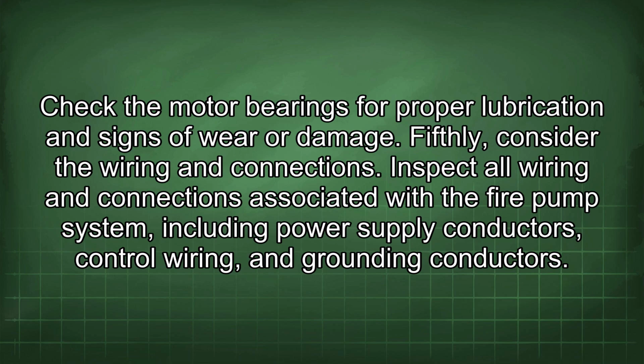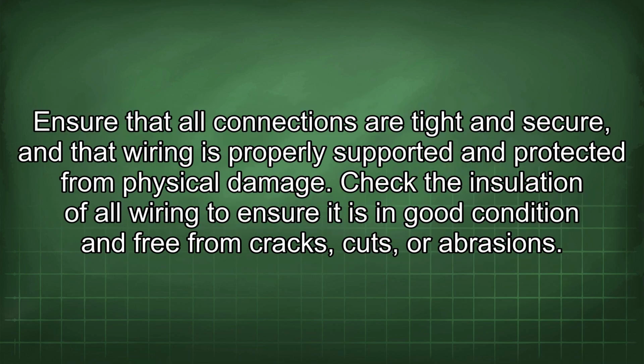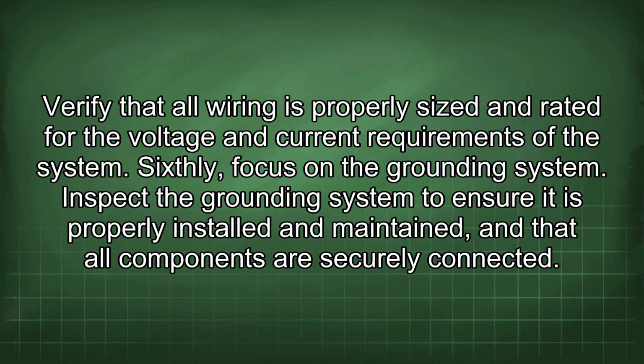Fifthly, consider the wiring and connections. Inspect all wiring and connections associated with the fire pump system, including power supply conductors, control wiring, and grounding conductors. Ensure that all connections are tight and secure, and that wiring is properly supported and protected from physical damage. Check the insulation of all wiring to ensure it is in good condition and free from cracks, cuts, or abrasions. Verify that all wiring is properly sized and rated for the voltage and current requirements of this system.